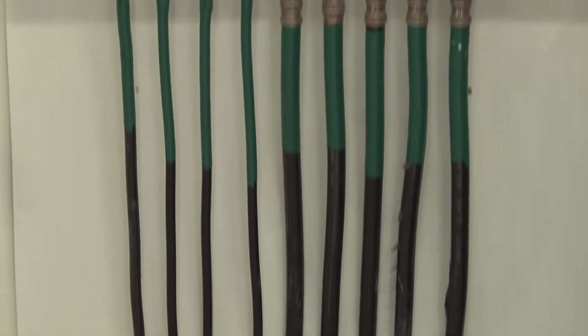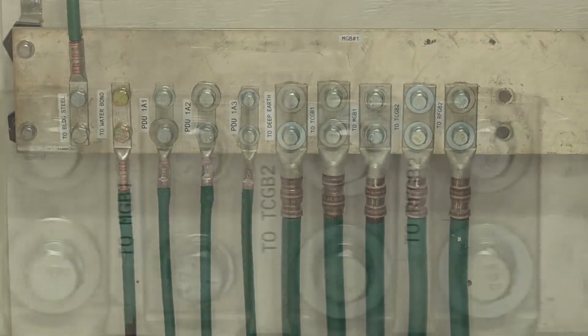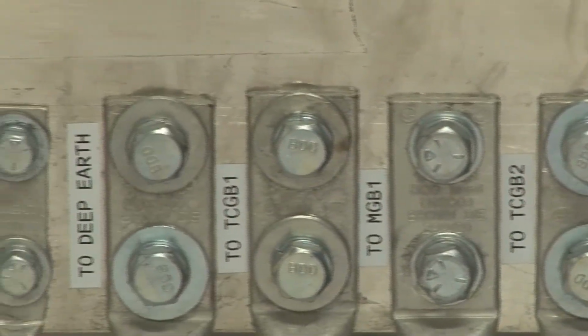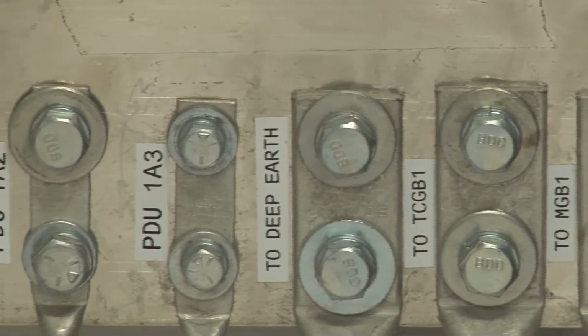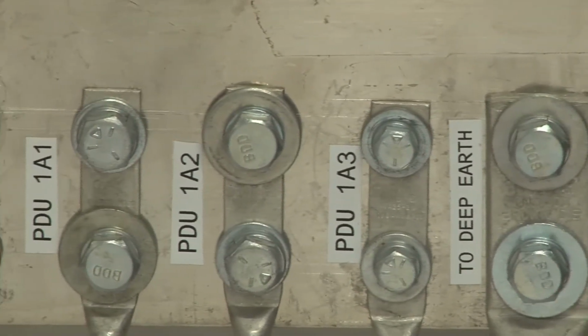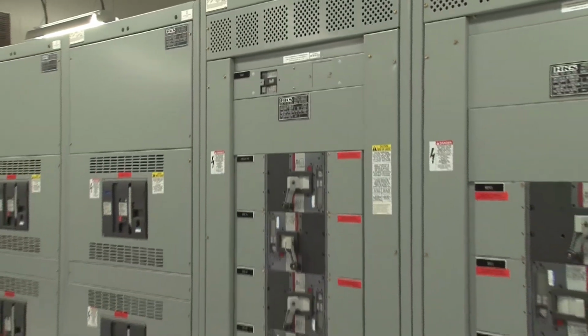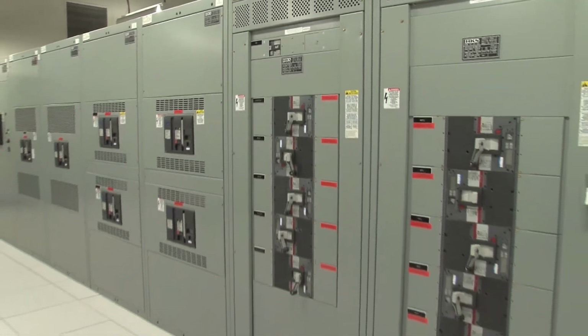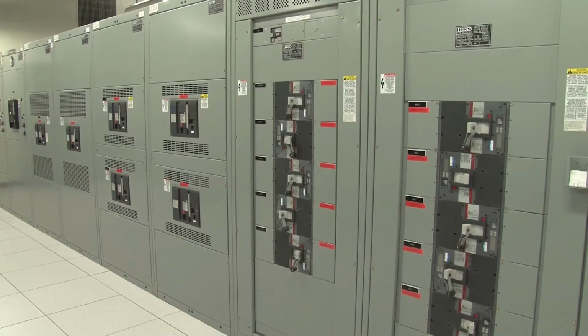We come into the building with a 500 MCM copper conductor, which goes to our main grounding bar. Each grounding bar after that is joined with another 500 MCM copper conductor. All electrical gear is grounded with a number 4 or bigger copper conductor going back to a ground bar. We do not allow a number 6, which is minimum by code. We have gone above and beyond that.